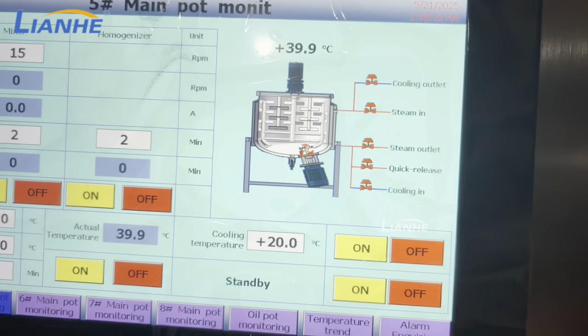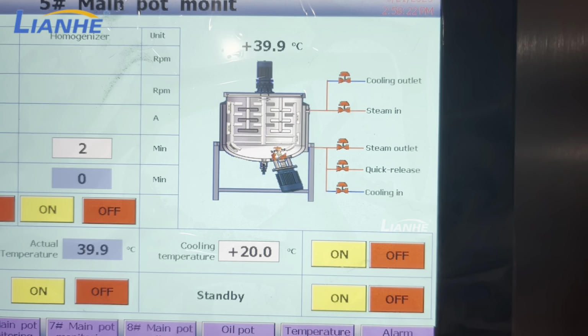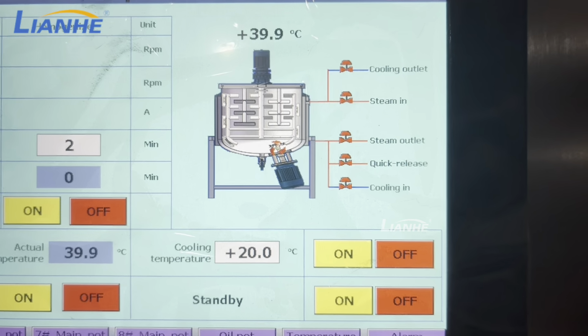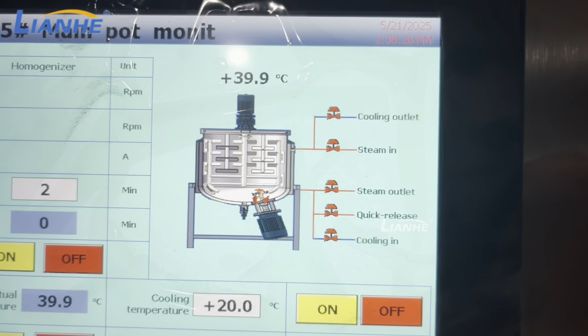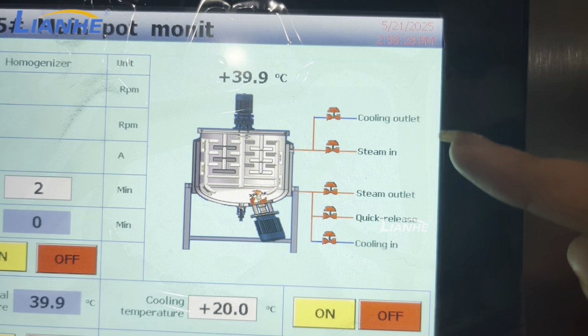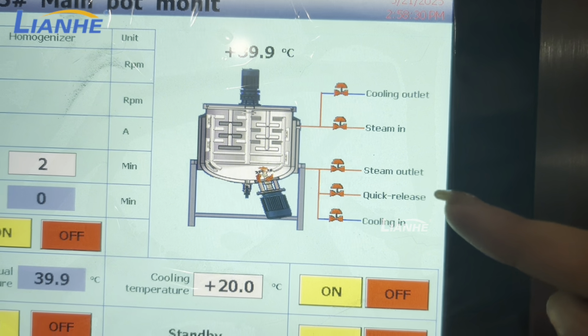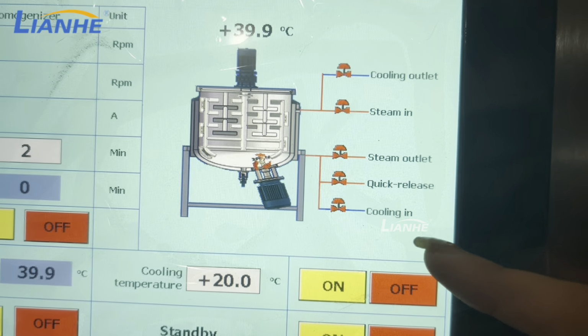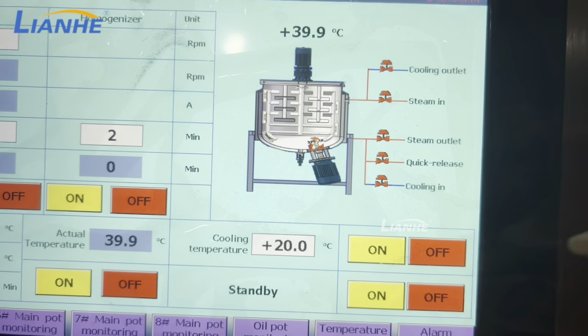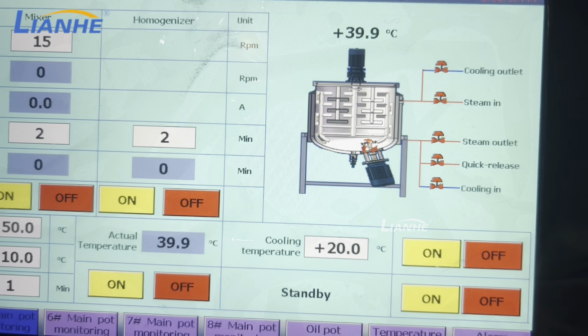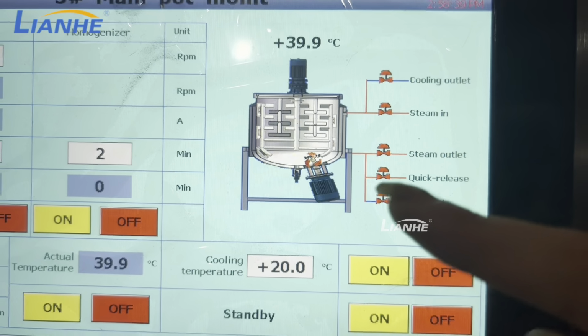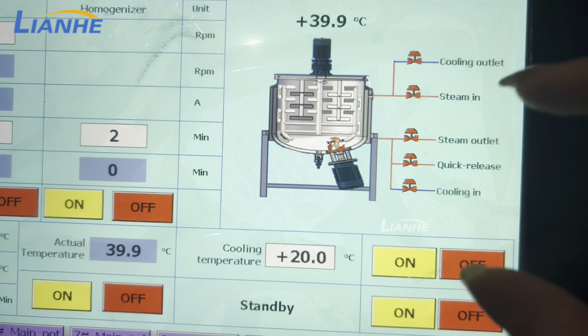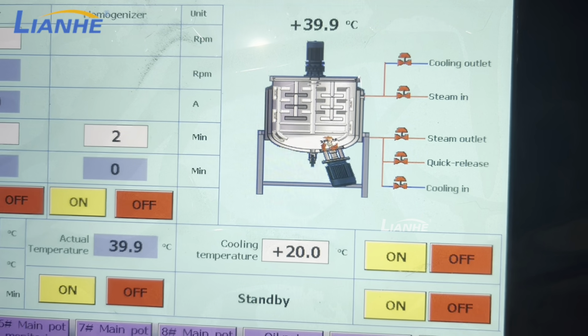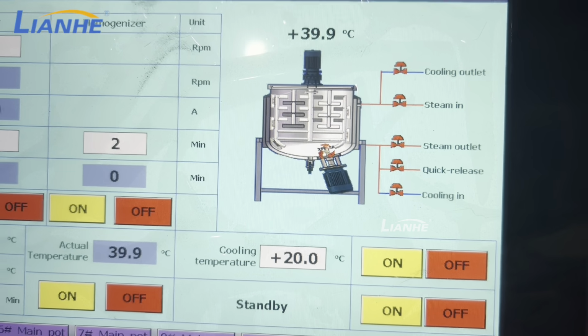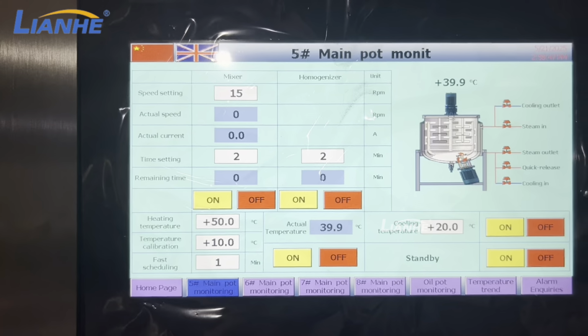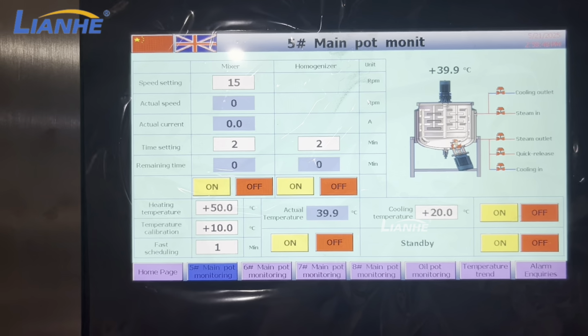You can check there are 5 pneumatic valves. Each valve controls different functions. Like this valve is for cooling out, steam in, steam out, quick release, and cooling in. Now, all valves are closed. You can check here. When the valve becomes green, that means this valve is open. Okay, now let me show you how to operate each function.